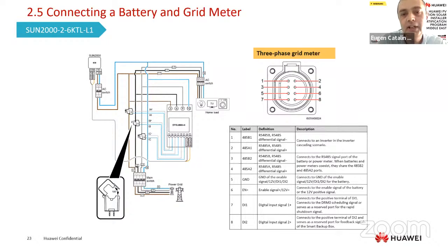The three-phase meter has 4 active powers: total power, and after that the power for phase A, B, and C. All these 4 should be positive. If the inverter is running, I need to add here, you need to stop the inverter from production, and you will measure in that place only consumption. This should be the measurement, and this means positive.